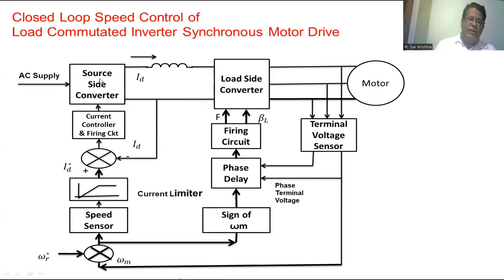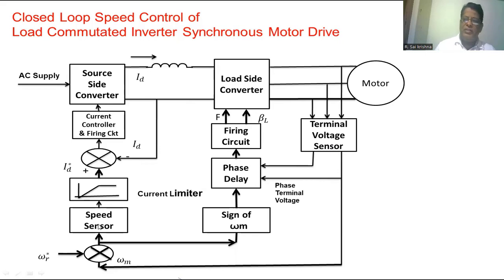For the source side converter, it is operated during transient operation such that the change in speed of the motor occurs at maximum torque, reducing the transient time period. In the closed-loop block diagram of the source side converter, the terminal voltage sensor gives the rotor speed, which is compared with the reference speed. The speed error is given to a PI speed controller. The output of the speed controller is given to a current limiter — the DC link current limiter. The output of the current limiter is Id*, the reference value for the DC link current. The DC link current is measured by a current sensor, and the error in DC link current is processed by the current controller, which generates the firing pulses to the source side converter.